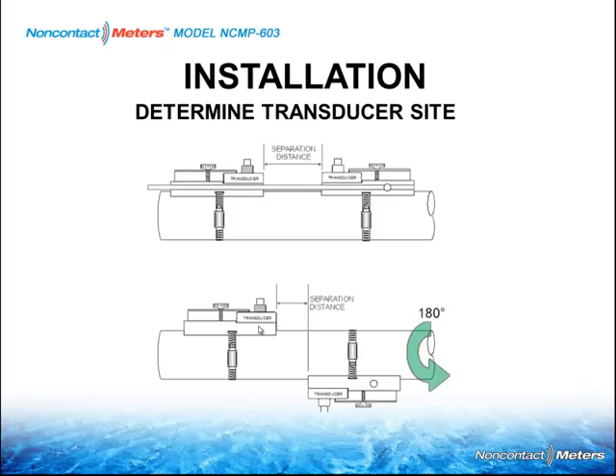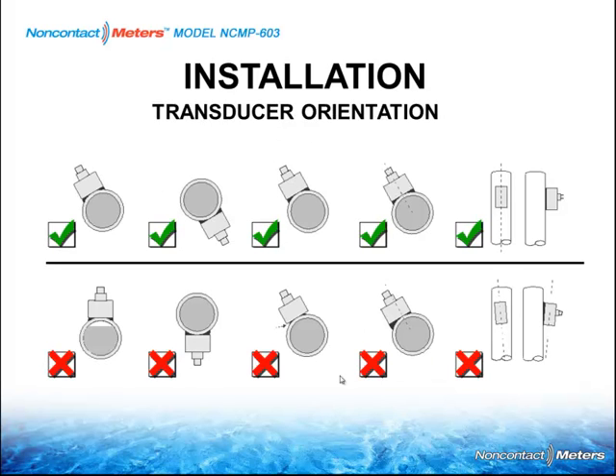Now remind you, the beam is about the diameter of a pencil. So you need to take this sensor, put it on the pipe, find 180 degrees on the other side, mark it off, and be on the same plane and the same transaxial angle here for this to work. More pictures about the transducer. Vertical, we don't mind. Vertical versus horizontal. Again, on the vertical, we're going to make sure we're square on the pipe there. And anything that's off of 6 o'clock is no good, and 12 o'clock is no good. So we need to put that on the pipe.